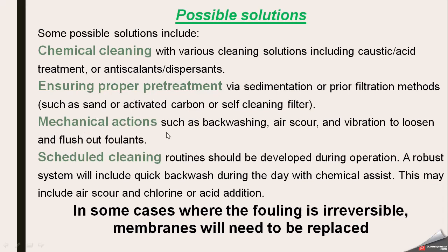Then some mechanical actions such as backwashing, air scour and vibration to loosen and flush out foulants. These are also steps of operation. During operation we will backwash, we will clean with air and vibration to loosen and flush out the foulants which are deposited on the membrane. Then scheduled cleaning. Routines should be developed during operation. This was explained in the previous video which dealt with the operation and backwashing and flushing of the membrane.